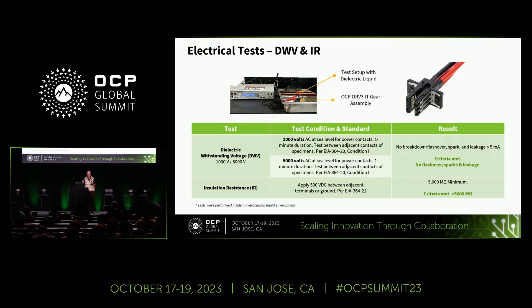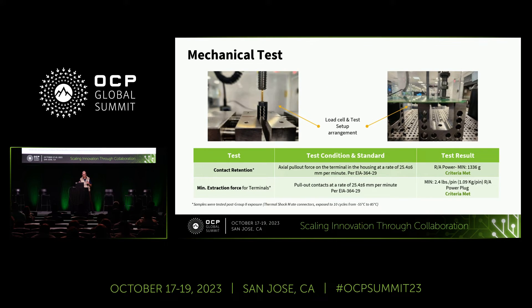For our post-tests, we did dielectric tests and insulation resistance — all passing. The fluid in many ways improves the consistency of the product over time, acting almost like a lubricant with a number of positive attributes. However, lubrication could also hurt us in areas like contact retention, where mate and demate forces could be substantially changed by having that lubricant introduced to the interface. In these instances we passed, but all of these areas are opportunities to refine or change connector design to optimize for the fluid environment.